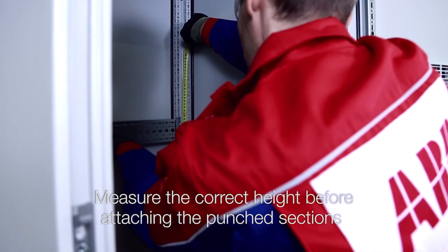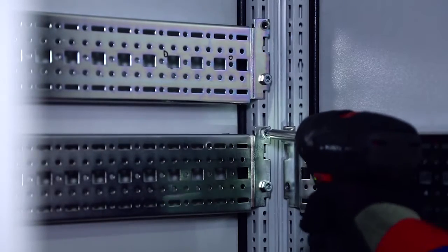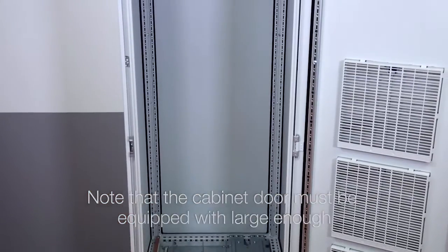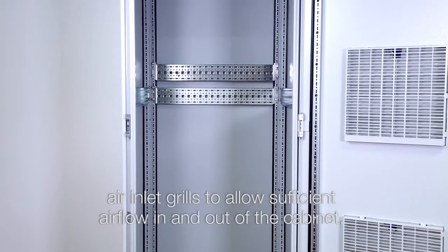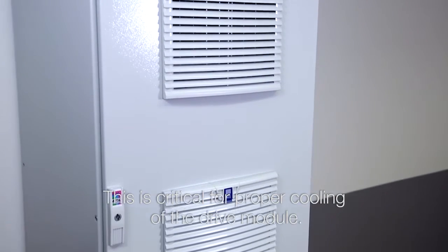Measure the correct height before attaching the punched sections to the cabinet frame. Note that the cabinet door must be equipped with large enough air inlet grills to allow sufficient air flow in and out of the cabinet. This is critical for proper cooling of the drive module.